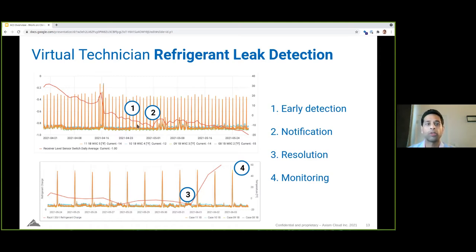While we're tracking receiver level and normalizing that with weather, heat load, and other factors, there's a slow leak happening here. That leak was invisible to the store's PPM sensors. There are a limited set of PPM sensors in the store, meaning they can detect refrigerant based on its concentration in the air, but it's difficult to place those sensors everywhere, and we're talking about miles and miles of piping that goes into the stores.